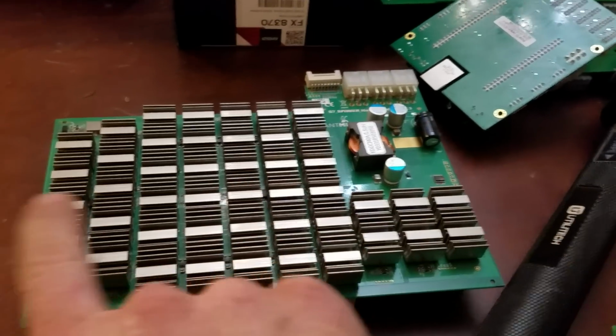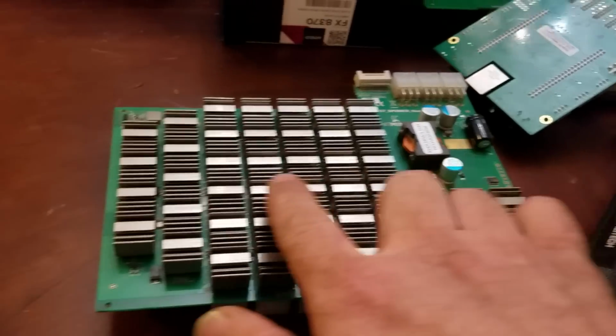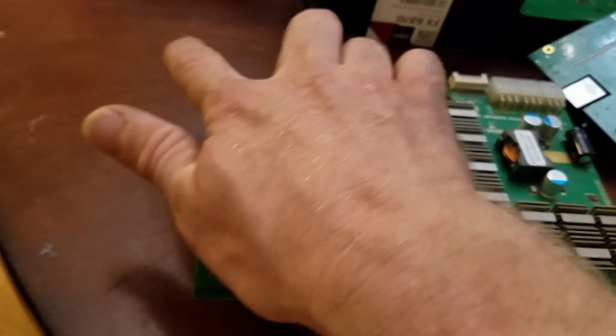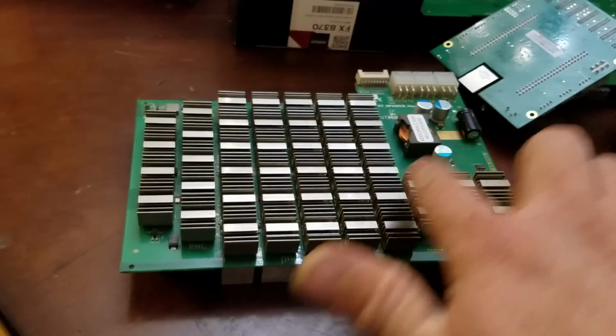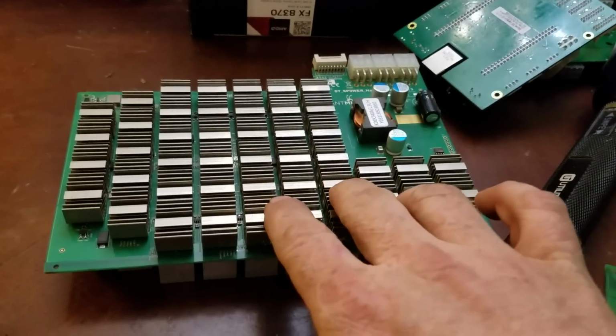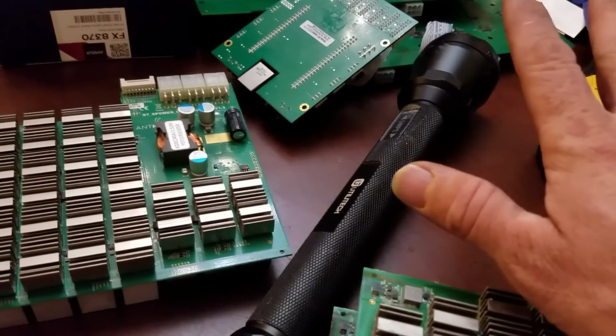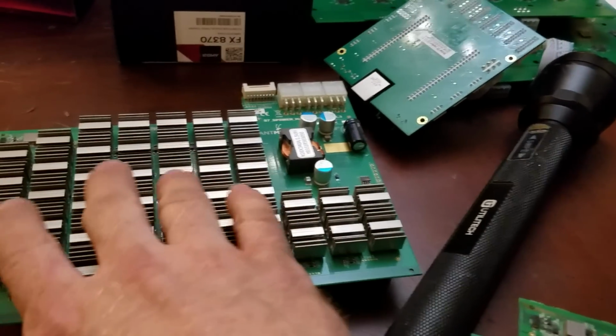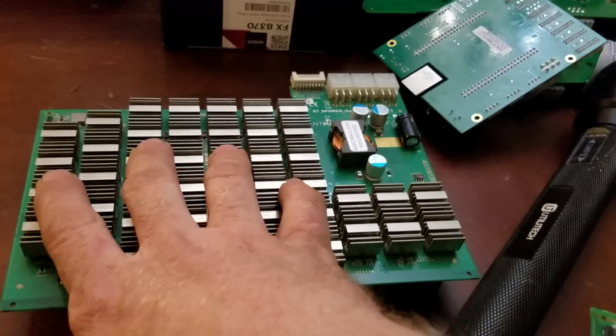And so what we get is, on the end cap, you've got the fan running, and it'll blow some around, but it's starving for air. So this hot air will come back around and go back through, and you'll get a recycling of hot air, even though the air off to this side is cooler. It's too much work, and it's too much pressure within the housing.